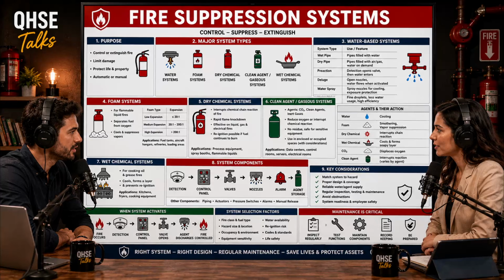Because pure water is actually an insulator, but water in the real world is full of dissolved minerals and salts, which makes it highly conductive. So if you use water on a live 480-volt electrical panel, the person holding the hose or the extinguisher is acting as the ground. The current travels straight back up the stream of water into the human body. It's a severe electrocution hazard. So we rely on dry chemicals and clean agent gases.